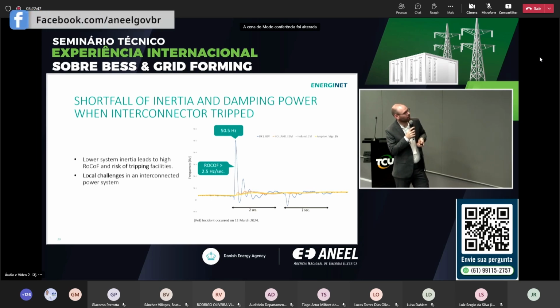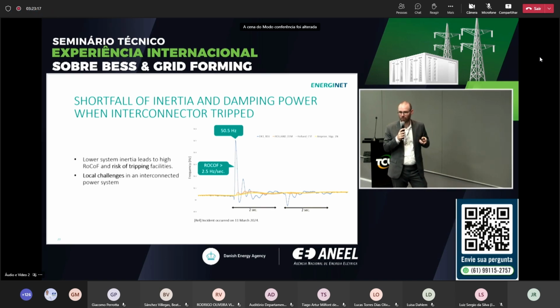The last example is from the Viking Link connection to the UK I mentioned before. It's a 1.4 gigawatt connection, the biggest one we have in Denmark, and it has actually tripped several times since it was put into operation a few years ago. This time there was a problem on the UK side, not the Danish side, which meant we had to redirect 1.4 gigawatts very, very fast, and this caused a very high rate of change of frequency.